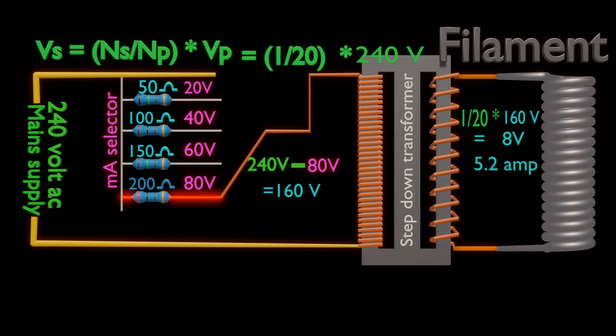But for other types of diagnostic procedures, where high amperage is used at very short intervals, control of tube current is achieved by use of multiple resistors.